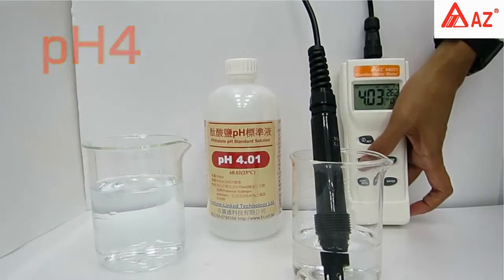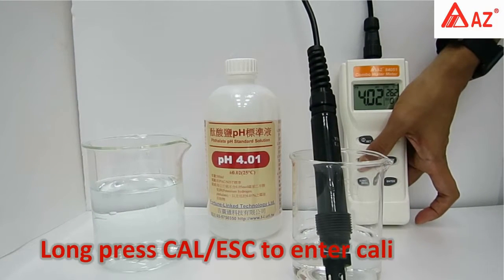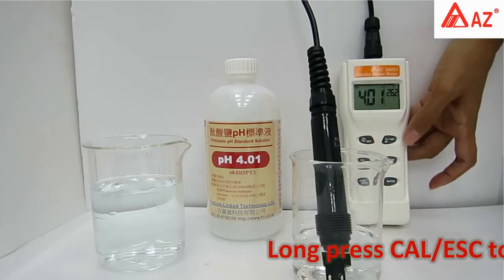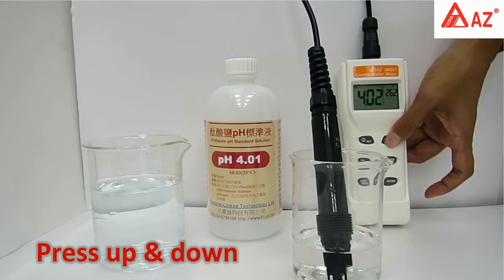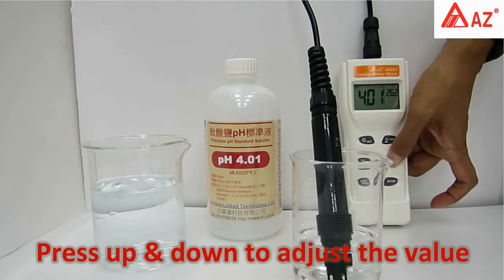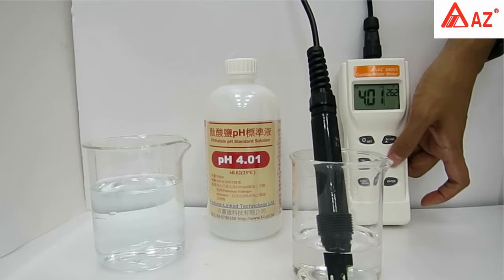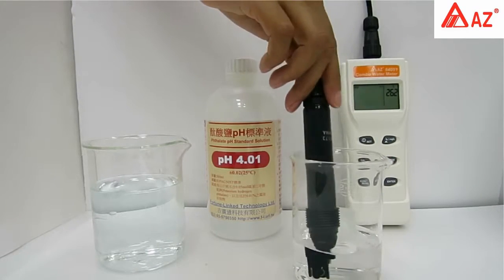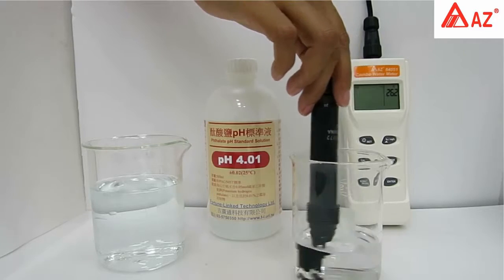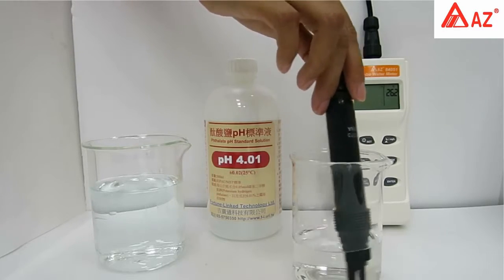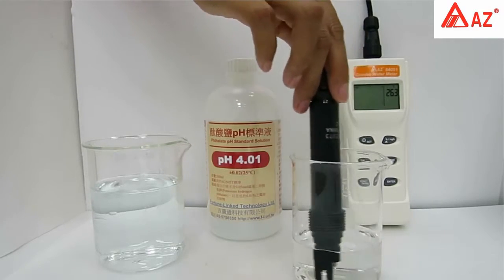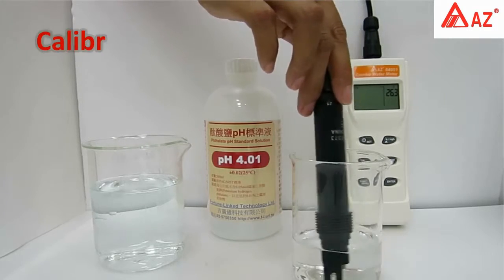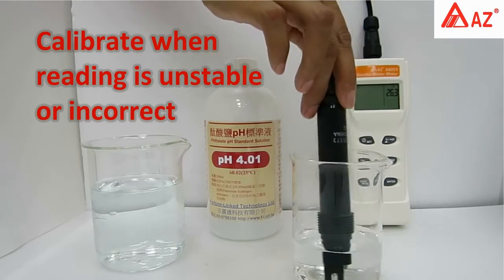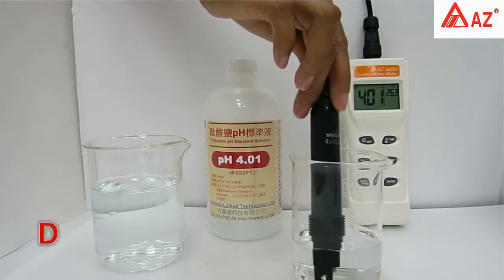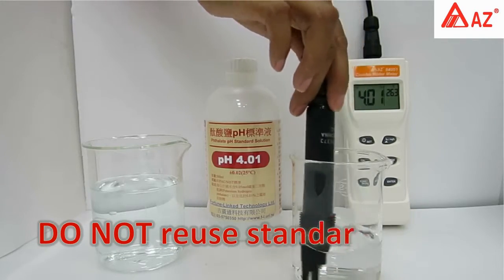pH 4. Long press cal to enter calibration. Set the standard value using the up and down keys. Use a transparent container and make sure the pH electrode is completely immersed in buffer. Stir gently to get a homogeneous condition. Calibrate when the pH reading is unstable or incorrect. Do not reuse standard buffer.